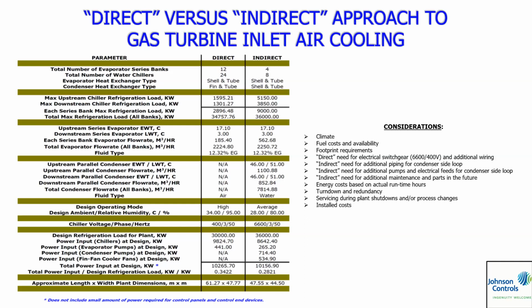But anyway, what this analysis is showing, when you look at the different operating conditions and you factor in all the power, the centrifugals, if you look at it in kW per ton for the plant, okay, kW per ton for the plant was 2821 versus 3422. Advantage centrifugals, that makes sense, right? If you look at it from a footprint standpoint, the centrifugals had a smaller footprint than what was required for all the air-cooled chillers. Okay. However, well, let me stop. Which one do you think won this value analysis? Always about the damn money, right?